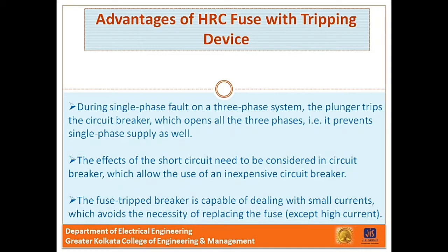Next one, the effects of full short circuit current need not be considered in the choice of circuit breaker. And this permits the use of a relatively inexpensive circuit breaker. The last one, the fuse tripped circuit breaker is generally capable of dealing with fairly small fault current itself. Now this avoids the necessity for replacing the fuse except after highest current for which it is intended.